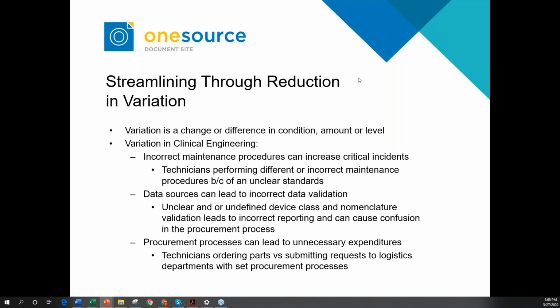So, streamlining your maintenance process through reduction in variation. Variation by definition is a change or difference in condition, amount, or level. And the variation in clinical engineering in general is just if your BMETs aren't doing the same thing across the board, it can cause an increase in critical incidents if technicians are performing incorrect maintenance procedures because of unclear standards. Say they're getting their preventative maintenance instructions from an old work order they found within your CMMS and just performing that without checking the manual. If they're going to an old database of manuals that your hospital has put together that aren't necessarily up to date, they could perform a maintenance procedure that's not in line with the current revision of the manual, which can happen quite often. So it's important to have a standard process.